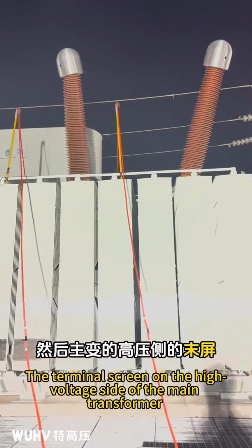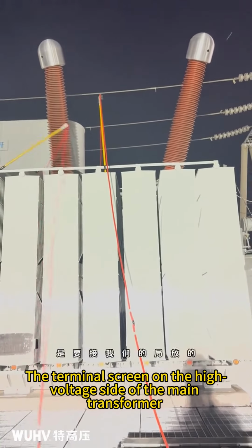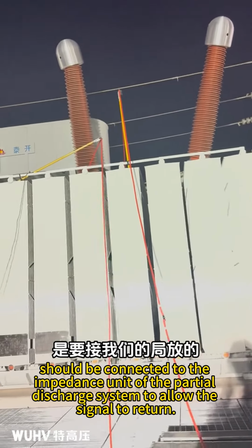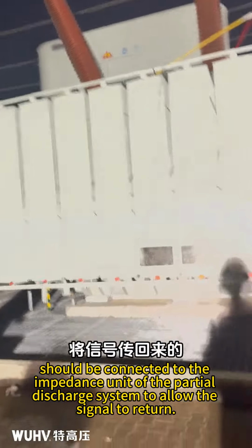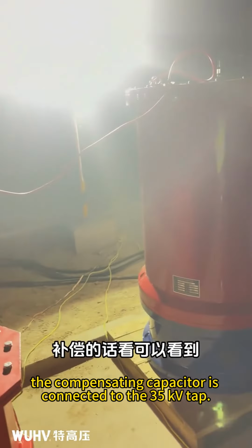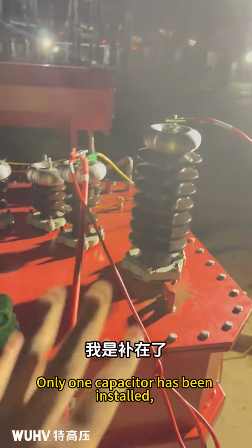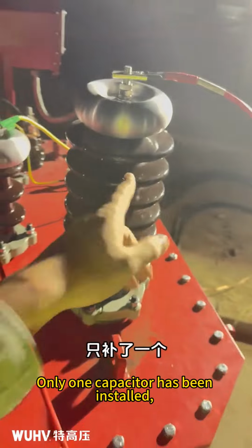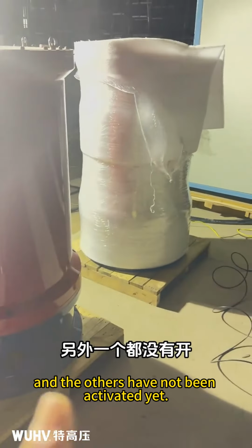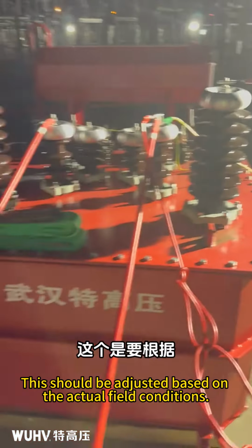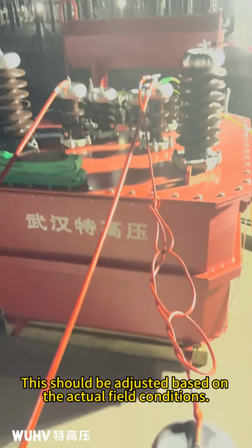The terminal screen on the high voltage side of the main transformer should be connected to the impedance unit of the partial discharge system to allow the signal to return. It can be seen that the compensating capacitor is connected to the 35 kV tap. Only one capacitor has been installed, and the others have not been activated yet. This should be adjusted based on the actual field conditions.